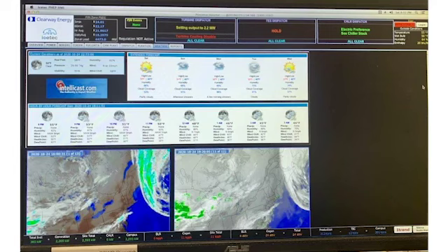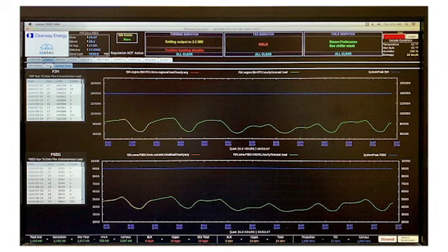And one of my favorite screens, because this is one of our primary focuses during the summer, and certainly the area where us as operators can provide maximum value, is the Icetec Scorekeeper screen, where to the left you'll see our PJM capacity charges, both the generation and the transmission charges. And you'll see those numbers, and I don't know if there's enough granularity in the picture, but you'll see that we had a banner year this year, and that our demand scores are going to be remarkable. With a facility that has a 6.5 megawatt total presence to grid potentially, during the times that were important, and I'll let Mike elaborate on this a little bit more, we were hardly on the grid at all, for 20 or 30 kilowatts.